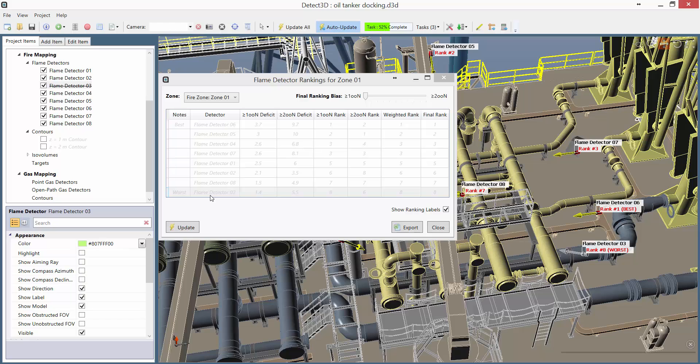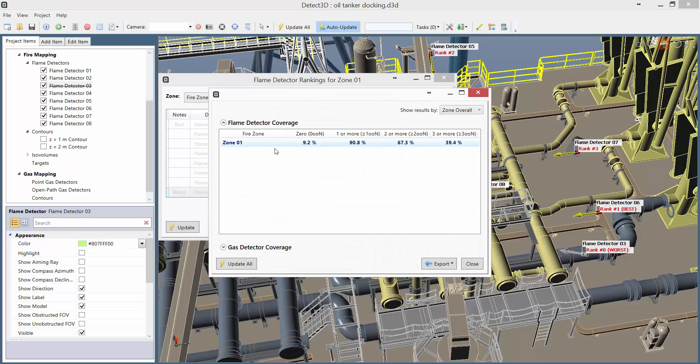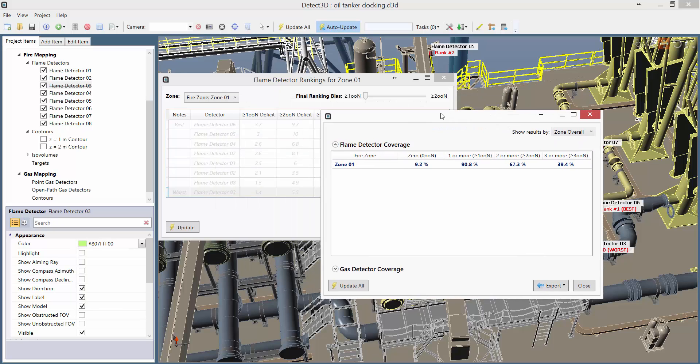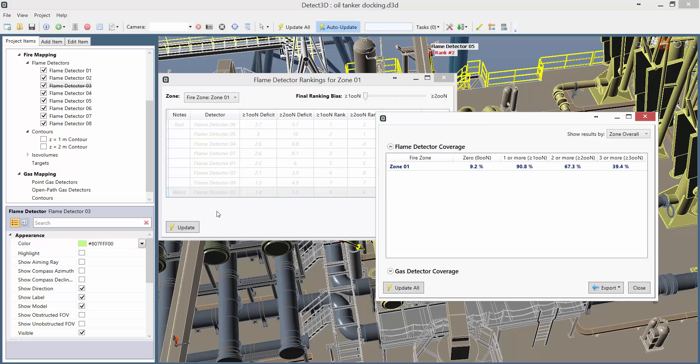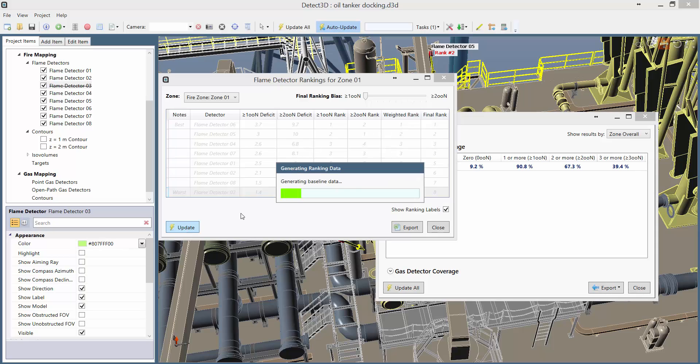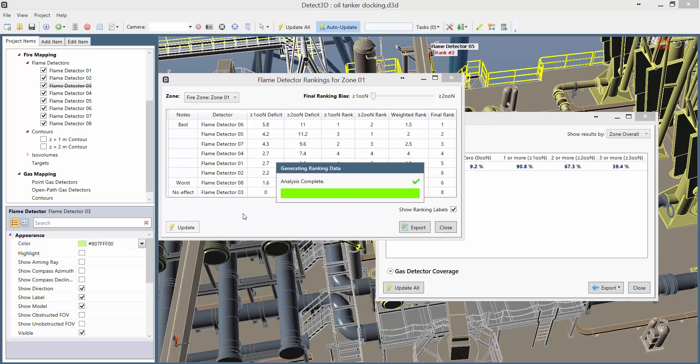Now that I've turned the Flame Detector 3 off, the simulation is just updating itself, and it's just completed, so we can have a look at the coverage. As expected, it's 90.8% for the 1 out of n coverage, which is above our target of 90% even though we switched off Flame Detector 03.